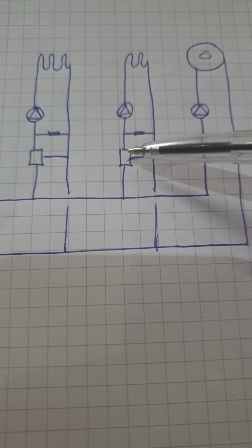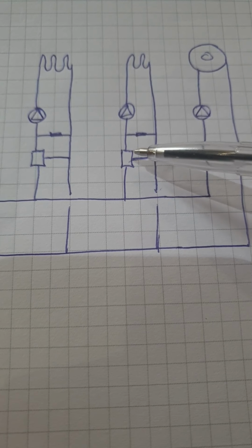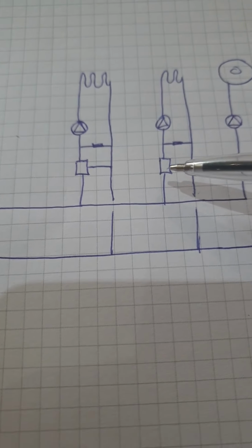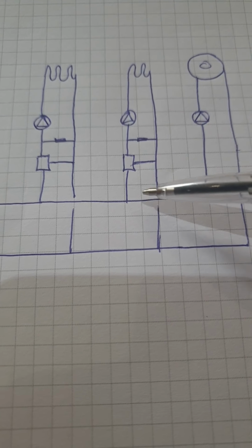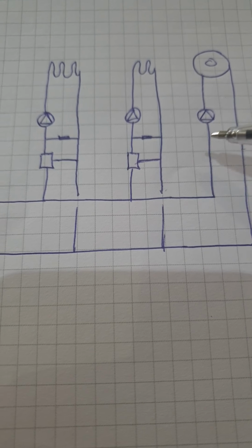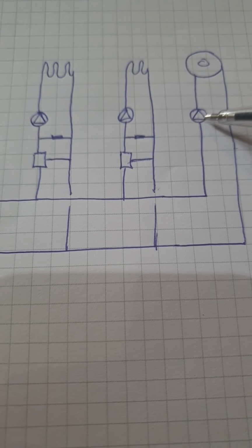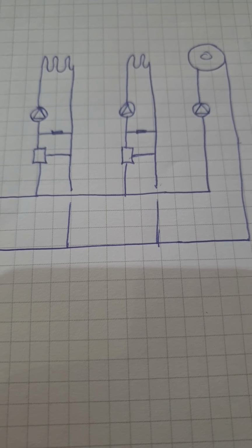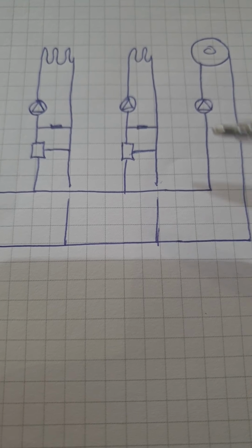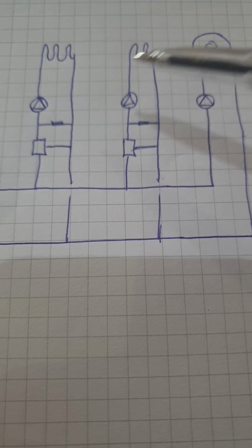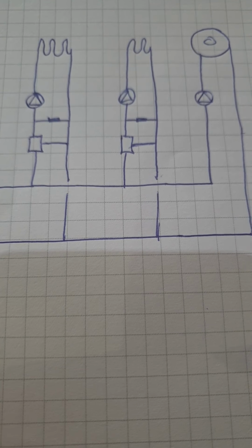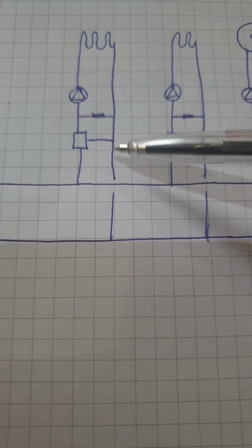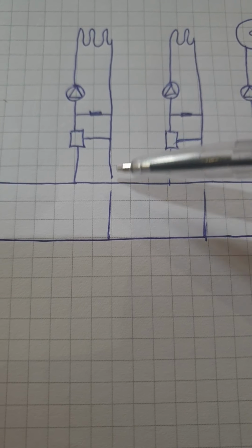If the highest temperature demand is one of these zones, the valve will be pretty much fully open and the boiler will be firing at the flow temperature of the circuit with the highest temperature demand. So this unmixed circuit is normally radiators, and these mixed circuits are normally underfloor heating zones, but you could use them on radiator zones, etc. And that's really it. So these are no different to an underfloor heating zone in effect. If you look at the design, these are actually drawn as underfloor heating zones.